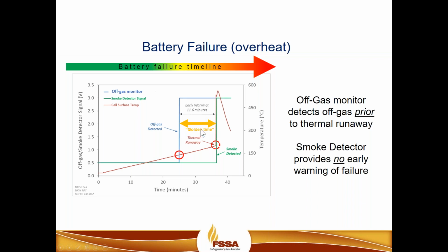So the smoke detector provides no early warning in this particular example. So as we mentioned, at stage 3 of battery failure, you have smoke, and that's really where the thermal runaway event occurs. So the smoke detector in this test provided no early warning detection. It was only the off-gas monitor that allowed us that golden time factor.